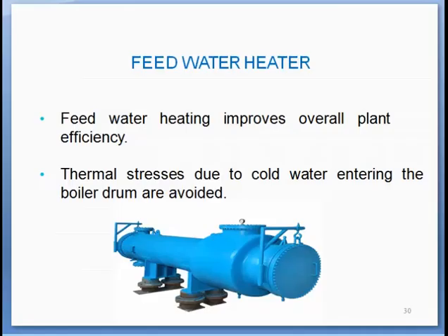Feed water heaters are basically heat exchangers which are used in a thermal power plant to preheat the feed water which is delivered to the steam generator. This preheating of the feed water reduces the irreversibilities involved in steam generation, and therefore it increases overall plant efficiency. It also prevents thermal stress in the boiler drum by avoiding entry of cold water. Feed water heaters are classified as HP heaters and LP heaters.